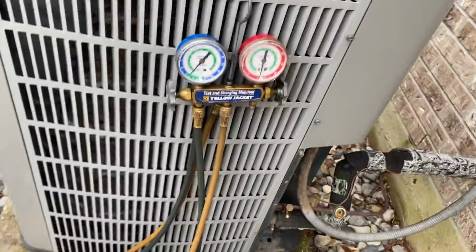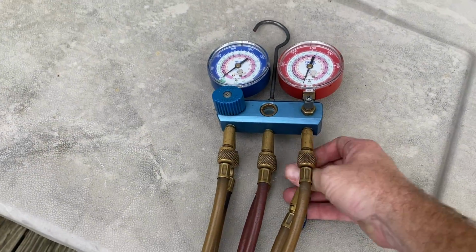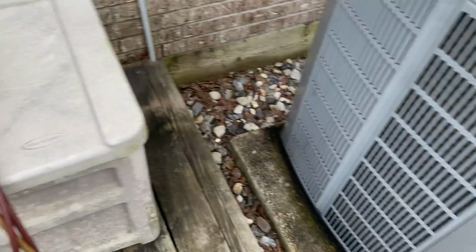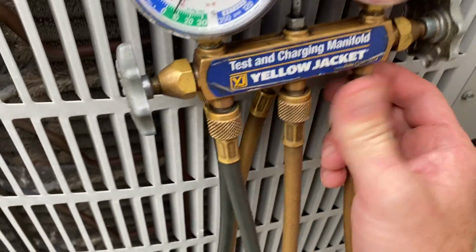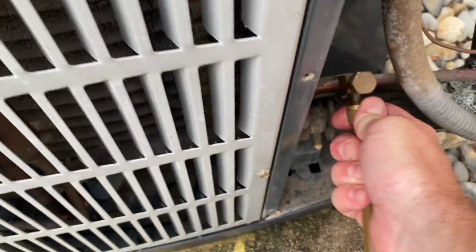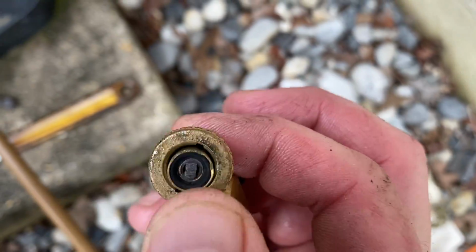Now, that little bit is called acceptable leakage. We talked the other day about you can have a certain amount come in or come out. Anytime it's just your hoses, that is acceptable. And there's another thing about leak detection. That's a percentage. And I'll see if I can't show you all that too. Let's look up. Okay. See here. There we go. Much better. I got to get a new O-ring. Where am I? There we go. Yeah, that O-ring's pretty worn out.